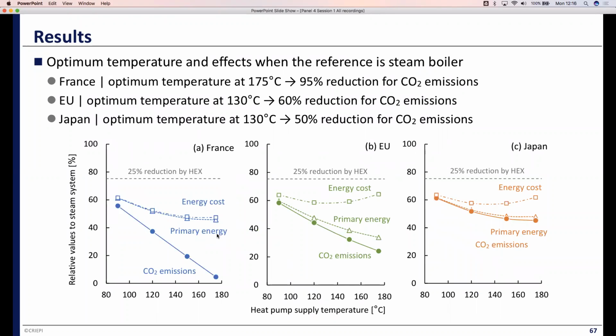Okay. Next, when the reference is a steam boiler, not only CO2 emissions but also primary energy consumption and energy cost are described. The optimum point is defined as the heat pump supply temperature which minimizes the energy cost. In France, the energy cost reduction effect is saturated from 150 degrees C. The energy cost is the smallest at 175 degrees C. If there is no difference in initial costs between 150 degrees C and 175 degrees C, it is better to operate the heat pump at 175 degrees C.